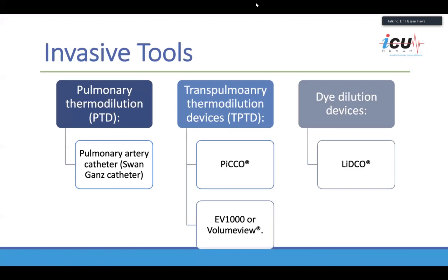Of the invasive tools, we have devices that utilize pulmonary thermodilution (PTD), and the only type we have is the Swan-Ganz catheter or the PA catheter. Or we have tools that utilize the principle of transpulmonary thermodilution, like PiCCO or EV1000 — also called Volume View by Edwards. We can also use dye dilution devices; for this we have only one device, which utilizes lithium, and we call it LIDCO.